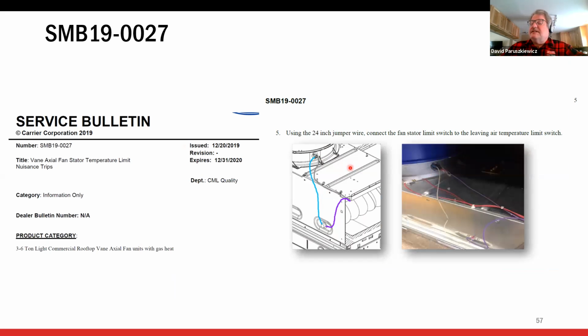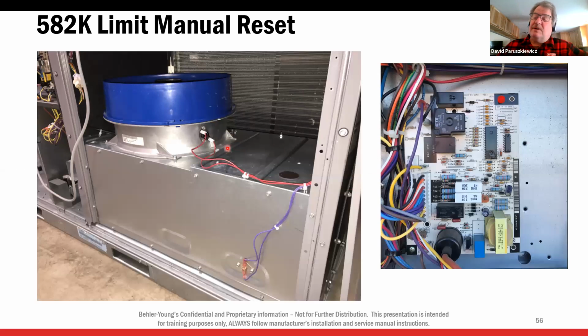So basically this bulletin tells you that you can replace this manual reset limit with an auto reset limit. What they want you to do is, these 2 red wires here, those are 24 volts. They're going to want you to wire nut those 2 wires together and then put the new automatic reset limit in series with this limit. So you'll take this wire off and put it here, and then you'll get a new wire 24 inches long and put it between the 2. So they're in series. That's to eliminate that manual reset limit. So again, tie those together, and then you're going to put the new limit here, in series with the main limit. And when we get to this in a minute, you'll see why.